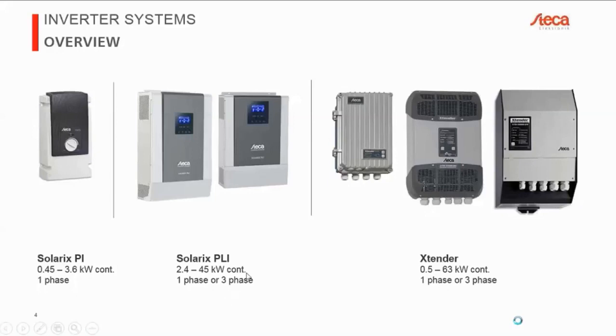Then we have the SOLARIX PLI. Here we have 2 models, a 24-volt and a 48-volt variant. One is 2.4 kilowatts, the other one is 5 kilowatts, and you can put up to 9 of them together. So that means you can have up to 45 kilowatts, 5 kilowatts times 9. And here we have the choice to either hook them up in single phase or in 3-phase mode, if you use more than 1 unit. Of course, for a single unit, it's always single phase. So if you want to build a 3-phase system, you will need at least 3 inverters. And then finally, on the high-end scale and the highest power as well, we have the XTENDER series of inverters. They come in 3 different sizes. I'll introduce them to you later on. And here we start at 500 watts for the smallest model, and 7 kilowatts is the largest model, and we can put, again, 9 of them together to have up to 63 kilowatts.